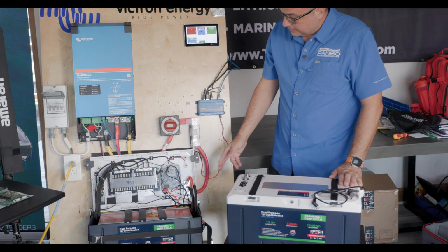So you might be wondering why that's done. One thing we're going to find out is that some of the spots where we've got single connections in this system are the hottest parts of the system. By giving 2 terminals in 2 places to make your connection, you're spreading that load out and able to reduce any hot spots in the system.